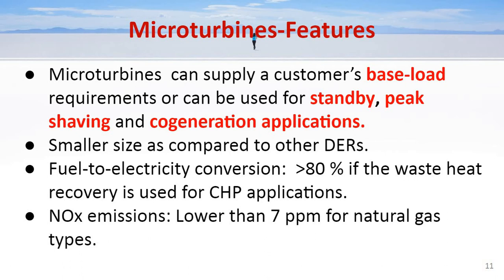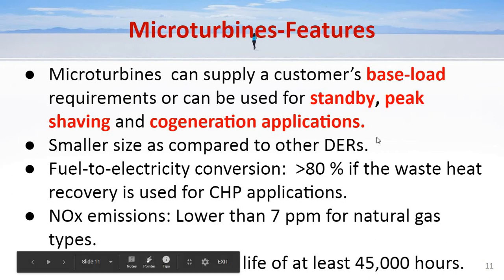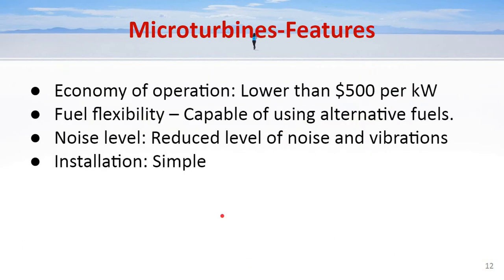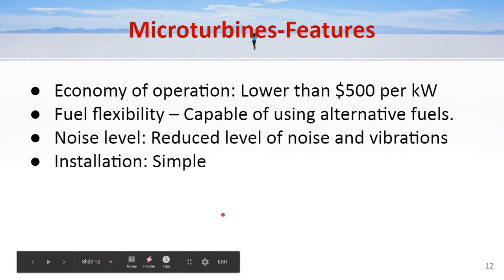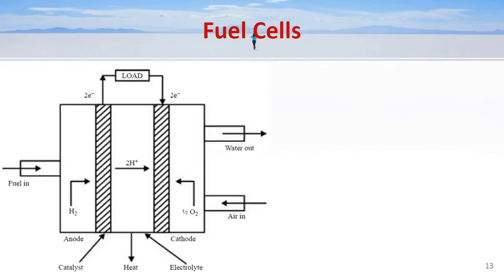The emissions are lower than 7 ppm for natural gas types, and it has a good life of approximately 45,000 hours. It is economical, fuel flexibility is there, noise level and vibrations are acceptable, and the installation is simple.